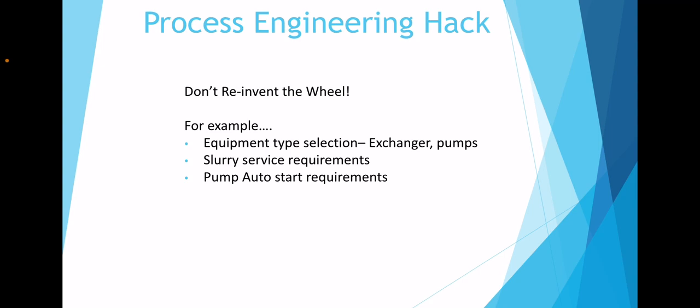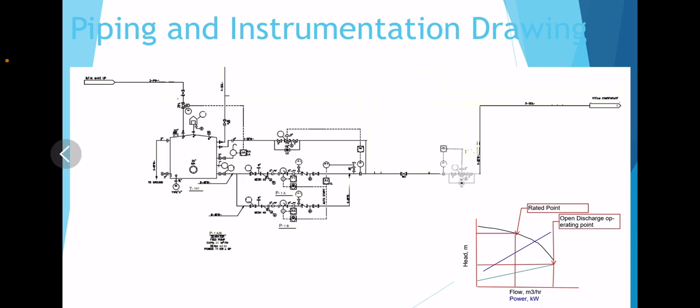Number 2 is slurry service requirements. In slurry services, it is important — particularly on pump discharges — to not place check valves, because check valves could choke up under the presence of slurry. Thirdly, let's look at pump auto-start requirements. In the previous sample P&ID, there is a pressure transmitter located on the pump discharge which senses the pressure. When it drops due to any problem, it activates the spare pump motor. So whenever one pump fails, the other pump would start automatically to maintain the flow.